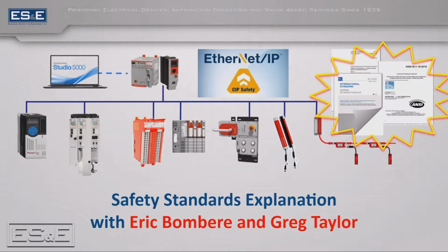With a lot of machinery, maybe most machinery, most of the time, the safe state will be to shut things off. With process control and maybe some aspects of a kitchen, we don't necessarily want to shut everything off. For example, if some ventilation needs to come on, or if you cross the bridge from machine safety into flame safety or fire detection or control extinguishers, it may be more important to turn things on or keep things running. So that might be a little different consideration than a more typical industrial machine.